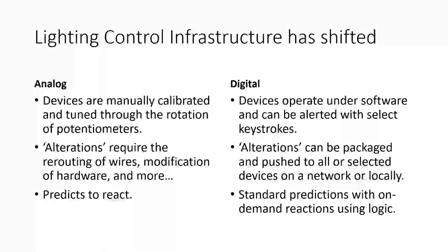Lighting control infrastructure has shifted from analog to digital. Analog devices are manually calibrated through the rotation of potentiometers — alterations require rerouting wires or modifying hardware, and they rely on predictions that are difficult to update. The digital version operates on software that can be altered with select keystrokes — alterations can be packaged and pushed to all or selected devices on the network. It uses standard predictions with on-demand reaction using logic that can be updated in real time, giving much more flexibility in how you design the lighting space to meet the demands of your occupants.